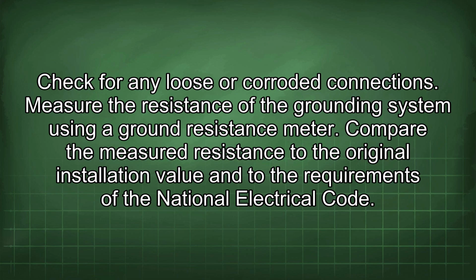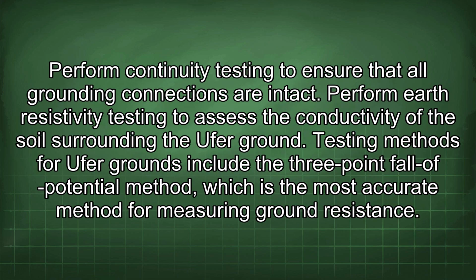Measure the resistance of the grounding system using a ground resistance meter. Compare the measured resistance to the original installation value and to the requirements of the National Electrical Code. Perform continuity testing to ensure that all grounding connections are intact. Perform earth resistivity testing to assess the conductivity of the soil surrounding the Ufer ground.